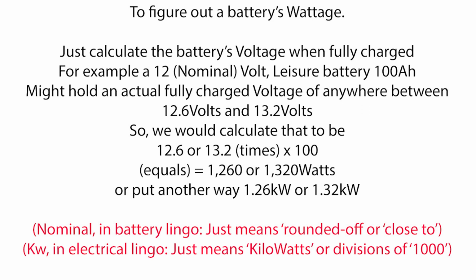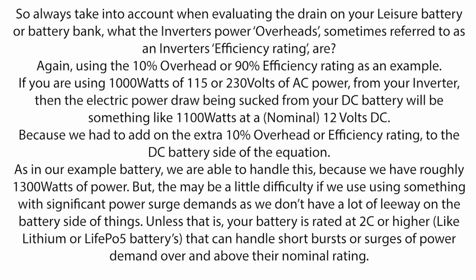So 12 times 100 equals 1200. So that works out to be 1200 watts, or 1.2 kW, or 1.2 kilowatts. This being roughly about the maximum wattage I might expect from my 12 volt 100 amp battery. As I stated earlier, 1000 watts AC plus the 10% overhead will equal 1100 watts draw from the DC battery. Maybe you didn't notice, but it's pretty much 1000 watts on both sides of the inverter conversion, both on the AC side and the DC side. Only difference being, on the DC side, there is a 10% inverter running overhead that bumps it up to 1100 watts. The wattage stays the same, it's the volts and amps and the electricity type that the inverter converts.